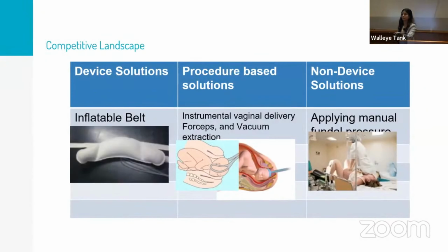and all these 3 chambers require different pressures. So it is really hard to manage this pressure, and the person who is on the control system needs to know what pressure is appropriate. It does not have a continuous monitoring system either. The device that I'm working on will have continuous ultrasound monitoring built in.